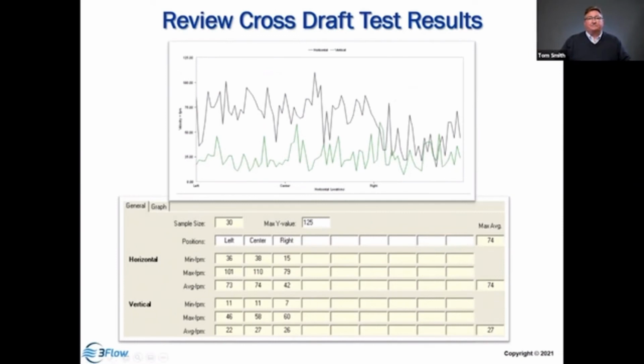In this example, we have our probe, this horizontal probe versus the vertical, and it shows it's very turbulent in the left, center, and right positions. When we look at the data, we see it range from 36 to 101 with an average of 73 on the left. In the center, the average was 74, and 42 on the right. So our max average was 74, significantly higher than 50% of our average face velocity. That's going to potentially cause an issue with containment. And we look at this turbulence as well.